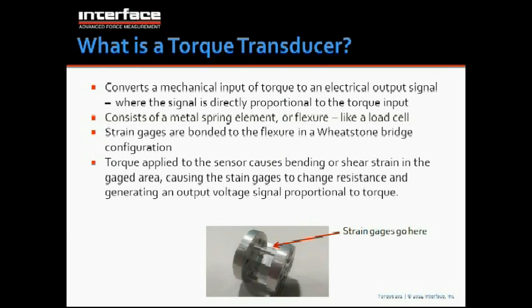So, what is a torque transducer? Many of us are familiar with load cells. Interface makes strain gauge based load cells and uses foil strain gauges for those sensors. A torque sensor is very much the same, except it reacts to torque instead of force. There's basically a metal spring element called a flexure, and that deforms under load. Strain gauges are bonded to the flexure in a Wheatstone bridge configuration, and when torque is applied to the sensor, it causes either a bending or a shear strain in the gauge area, and that causes the strain gauges to change resistance, and that generates an output voltage signal proportional to torque.